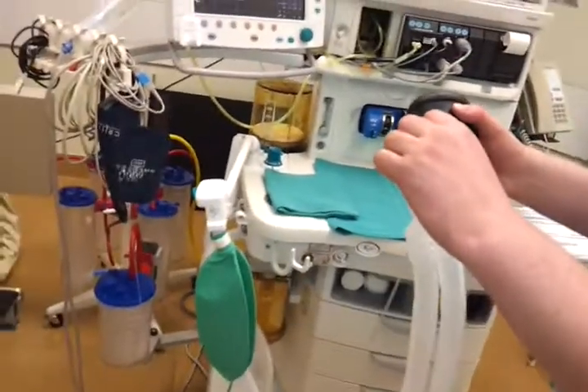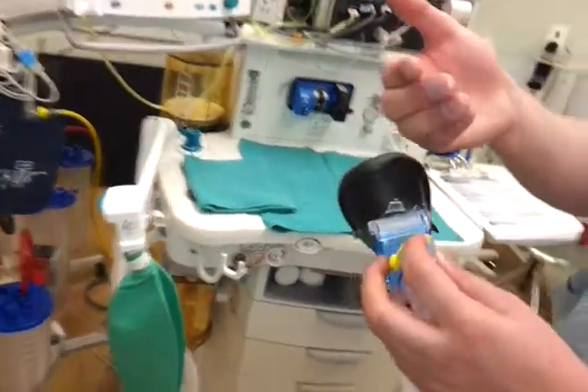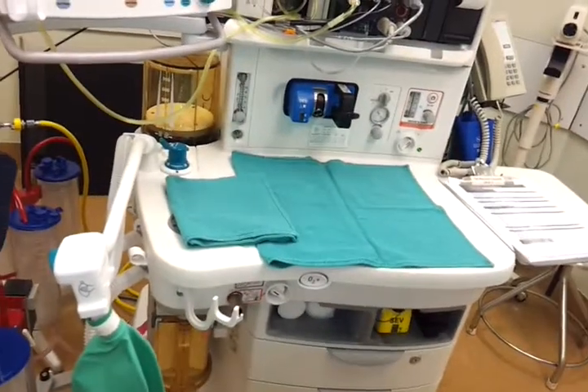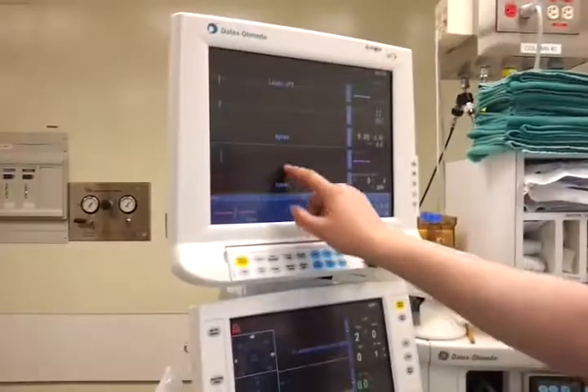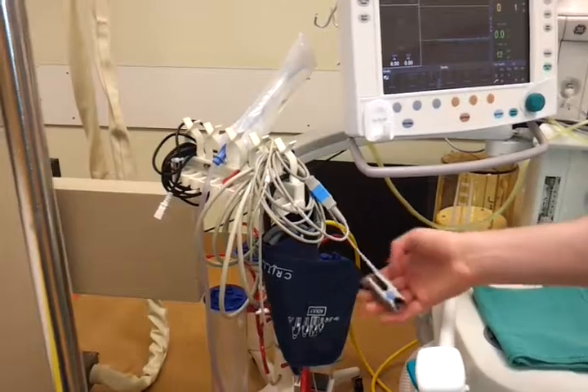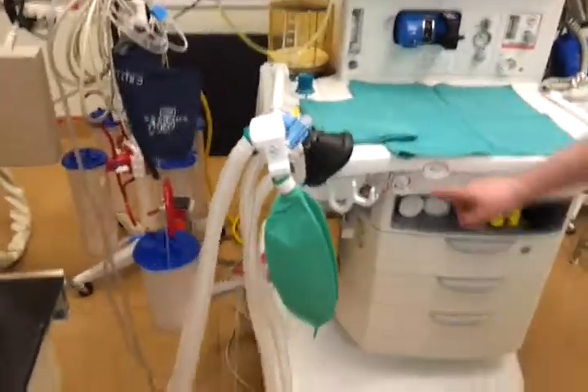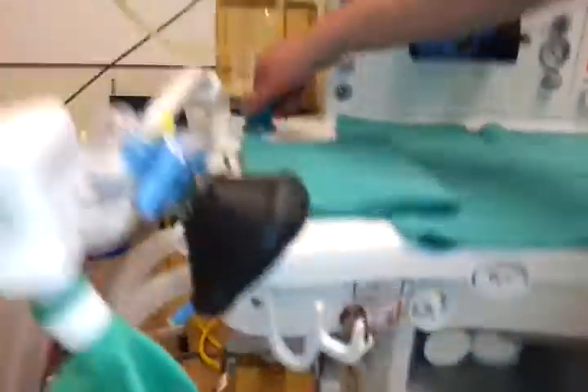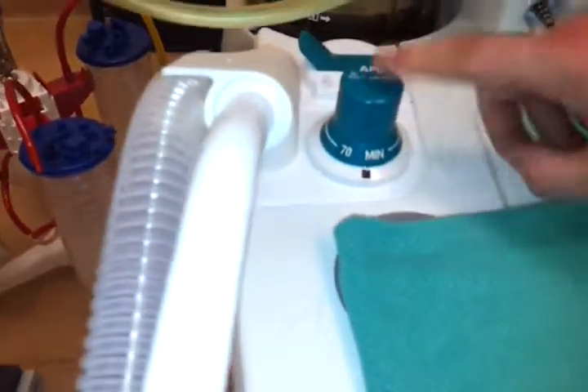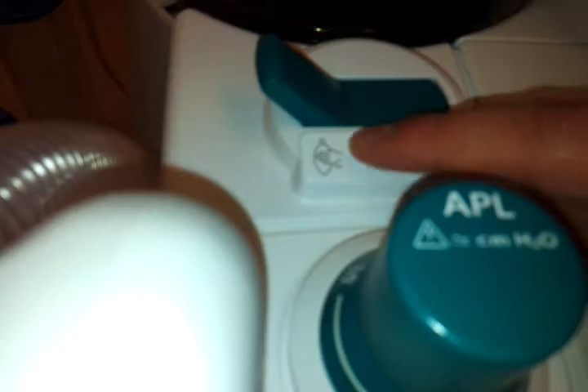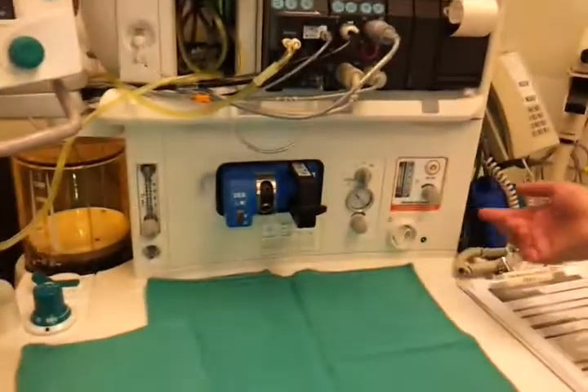Sometimes they get you to test the end tidal. You basically just take a mask and you put it inside of it and you breathe into it a few times and you'll be able to see the CO2 pop up. They also want you to test the pulse ox, so you just put it on yourself. That part's really easy. So the circuit's all ready. You want to make sure that it's set to circle, so it's pointed up, which it is. You want the APL valve to be set to minimum, which it is, and you want it to be set to bag. And the only other thing we didn't do is test the suction.